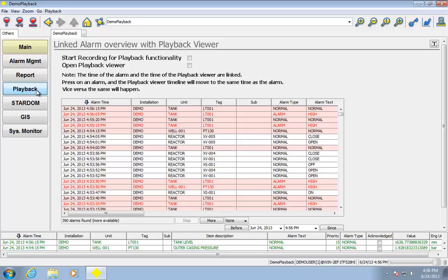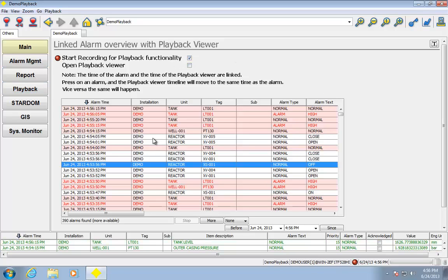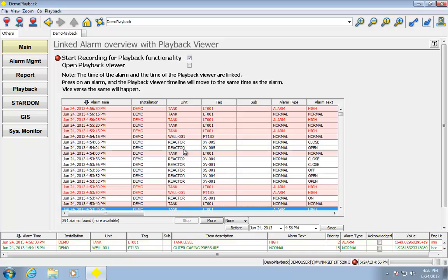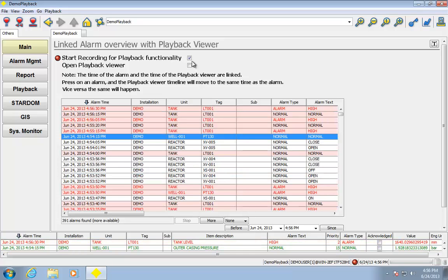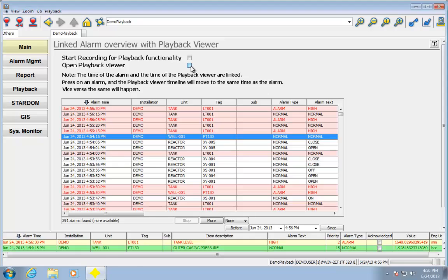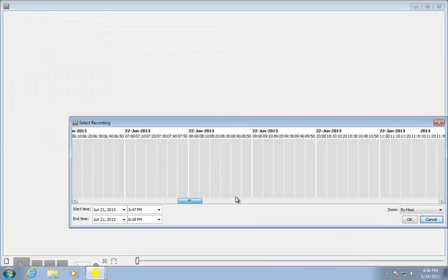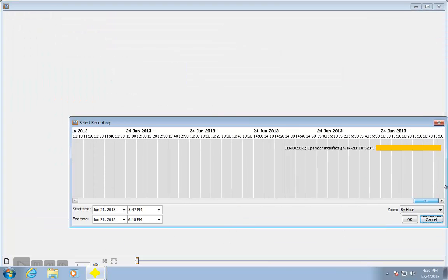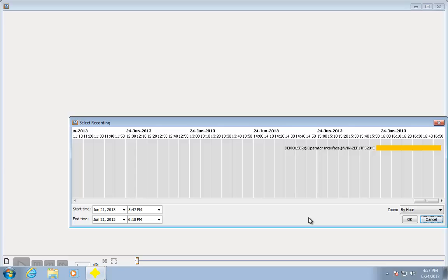So I've got another neat capability here called playback. I can go ahead and record what's going on on the screen, including mouse movements, where I click. And I can actually then do a playback on exactly what happened there. So maybe this is for training, maybe it's for just operator education, like say something happened out on a site and you wanted to know exactly what happened. If this recording was set and we set it to record every day and keep the most current day's worth of clicking and keyboard actions in place, then you could always play it back to see exactly what happened during a certain event that happened during the day.